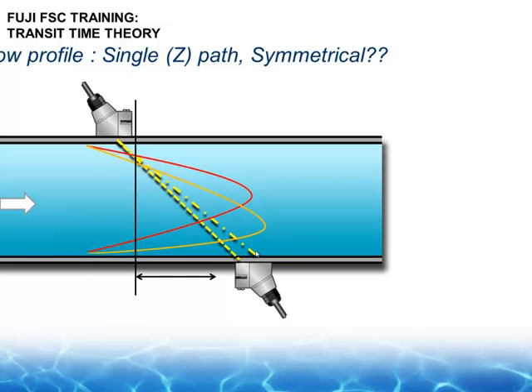I mean, there's something funky inside the pipe. There's a rock or pebble, or it's not smooth on the inside. You're going to get carried upstream or downstream. And in that case, you might be able to pick up a reading, but it won't be nearly as accurate as it is at the calculated reading.